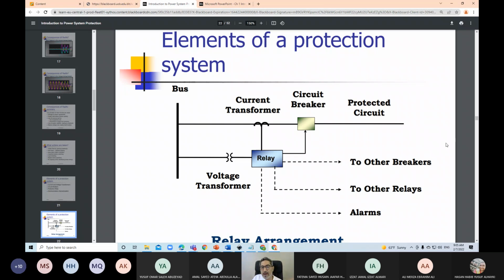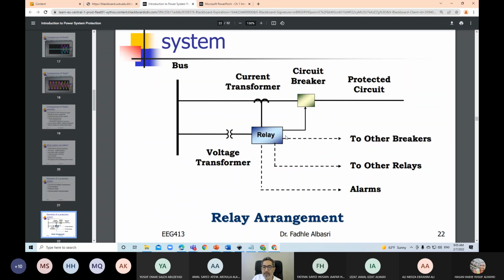Now, the circuit breaker in a high voltage system is a different component than a relay or a protective device. In low voltage systems, you don't have relays, you just have a circuit breaker. You don't have CT current and voltage transformers. The circuit breaker and the protection functions are integrated together in one device. So here we are not talking about protective devices in our houses, where a circuit breaker has the protection system and does the disconnection as one device.